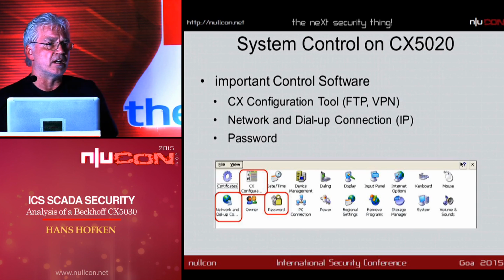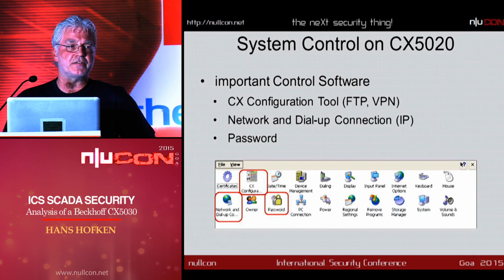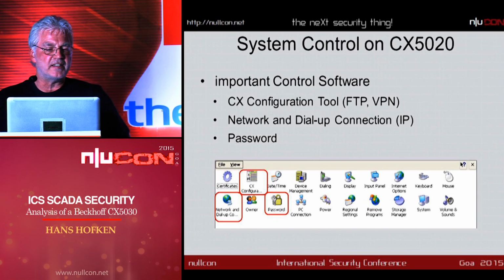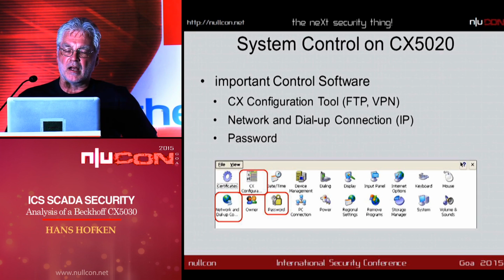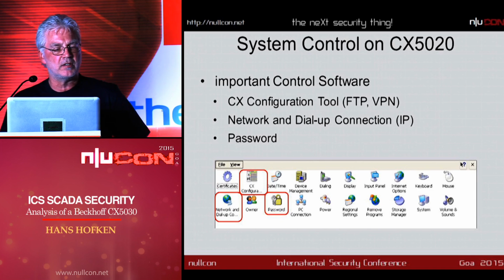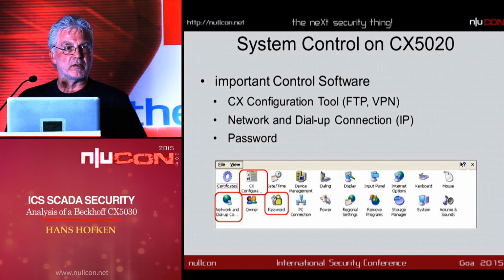To manage the PLC CX5020, you can use some tools from the Windows CE system. The most used tools are, for example, the CX configuration tool, which lets you configure an FTP server or a VPN connection. There's also a network and dial-up connection tool, where you can configure the IP address, or if you have a modem, configure the dial-up connection. Last but not least, there's a password tool so you can configure a password on this PLC.